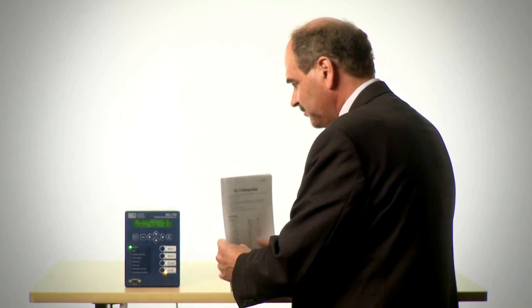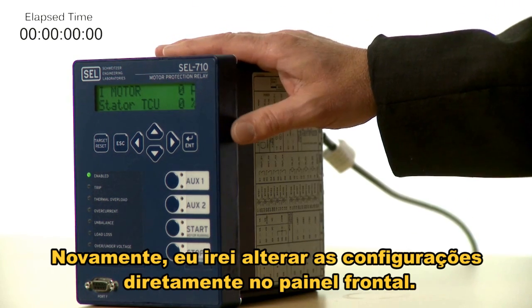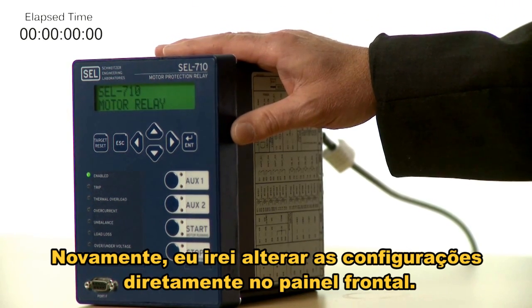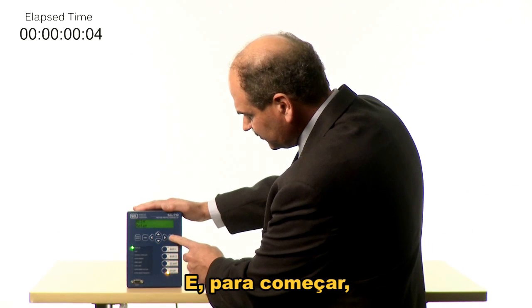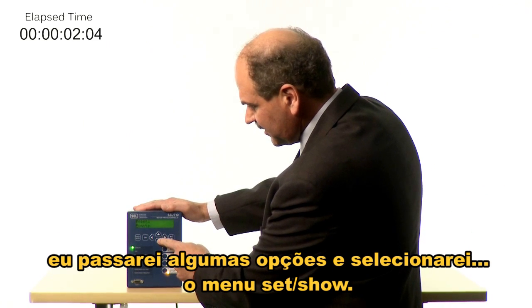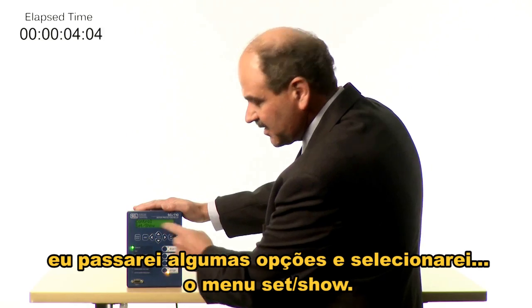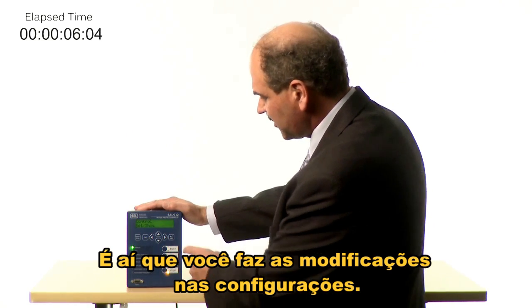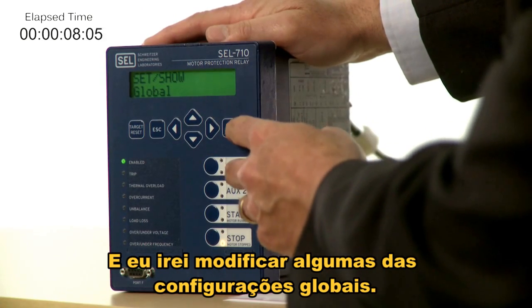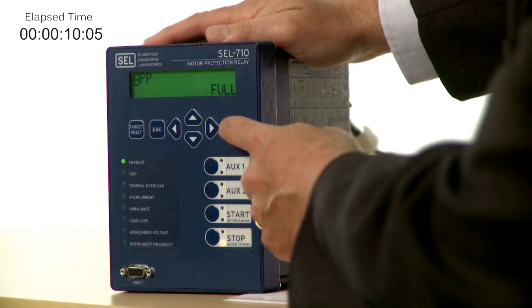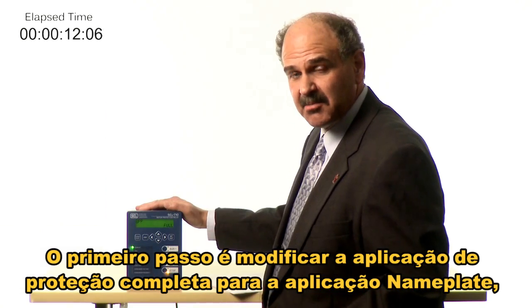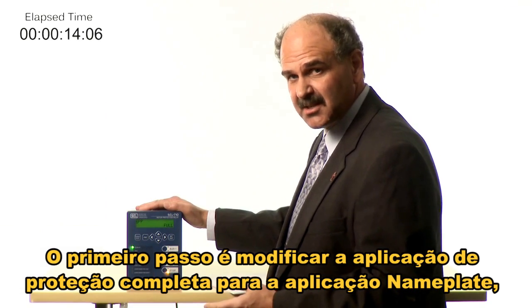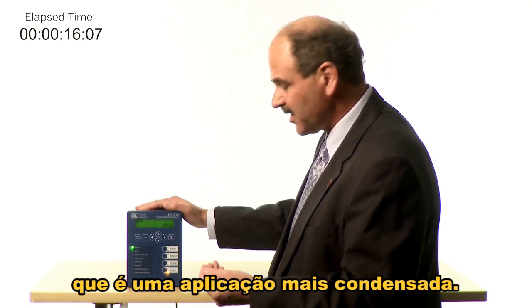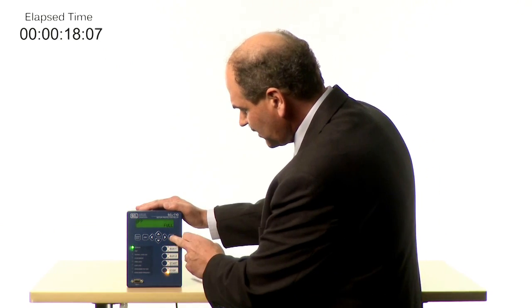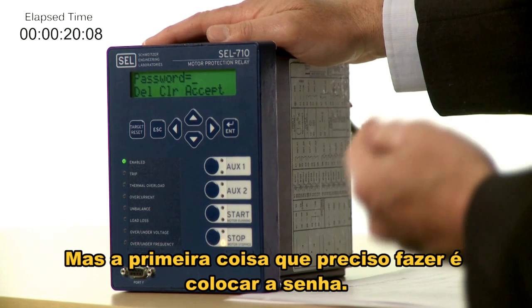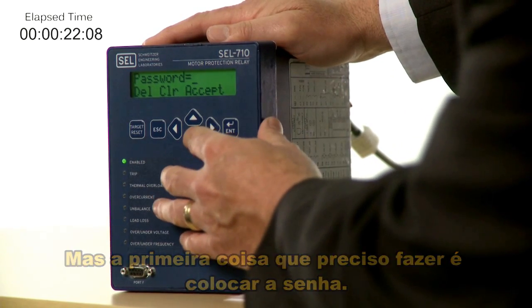Let's set that relay. Again, I'm going to do the settings right from the front panel. To get started, I'm going to select the Set Show menu. That's where you make the setting changes. I'm going to change some of the global settings. The first thing I'm going to do is change the application from a full protection application to a nameplate application, which is a more condensed application setting. But the first thing I need to do is enter the password.